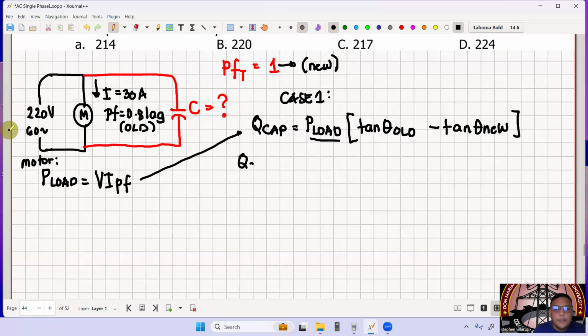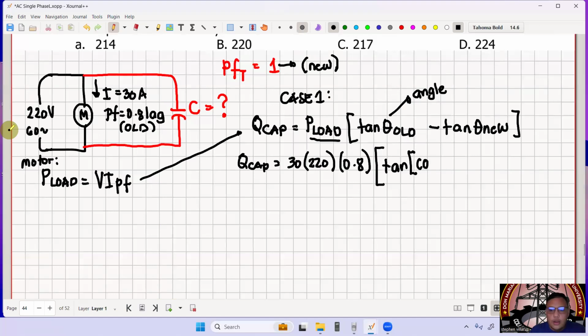So let's apply that here. Q cap is equal to 30 times 220 times 0.8. This is now your P load multiplied by tangent theta old. But what's your theta old? Take note, this is an angle, not 0.8 itself. So we need to get the inverse cosine of 0.8.